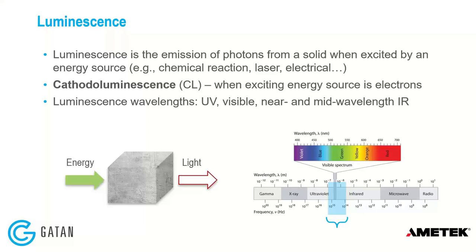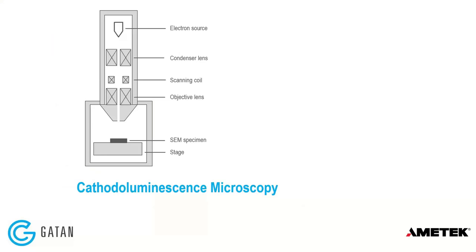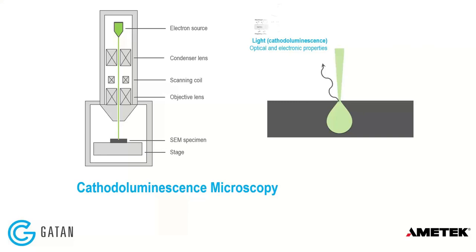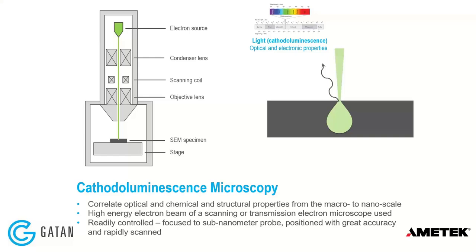Cathodoluminescence typically concerns itself from the UV into the near-mid wave IR. Here's a depiction of the electromagnetic spectrum with the region that CL is typically relevant highlighted. CL microscopy uses an electron microscope which impinges on a sample, creating what we call a generation volume, from which excited electrons in the sample drive a number of processes — including secondary electrons, backscattered electrons, and cathodoluminescence. It allows us to correlate optical, chemical, and structural properties from macro to nanoscale with very high spatial resolution.